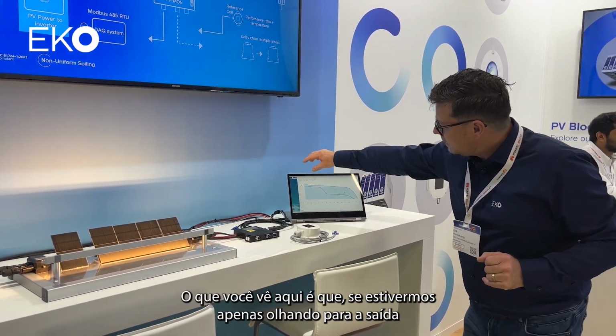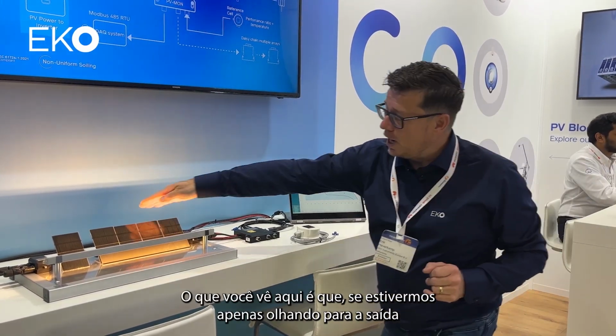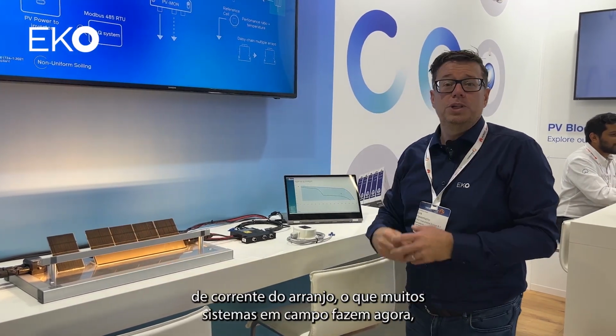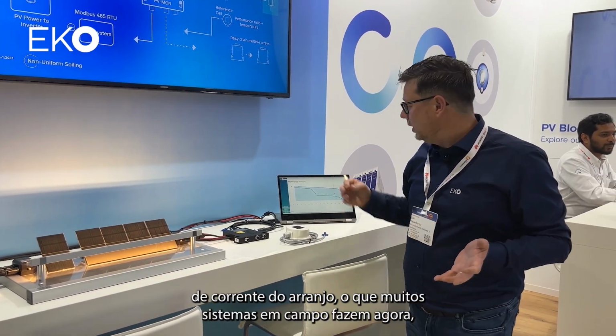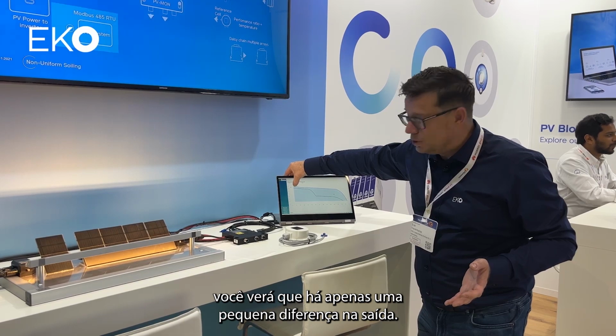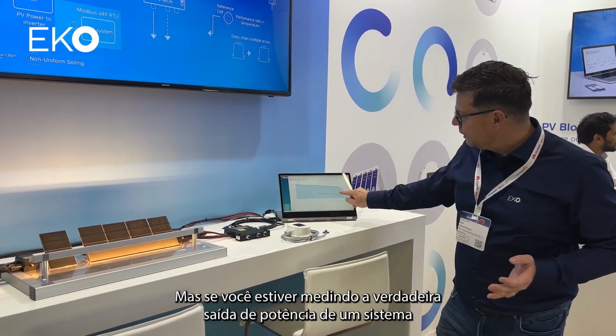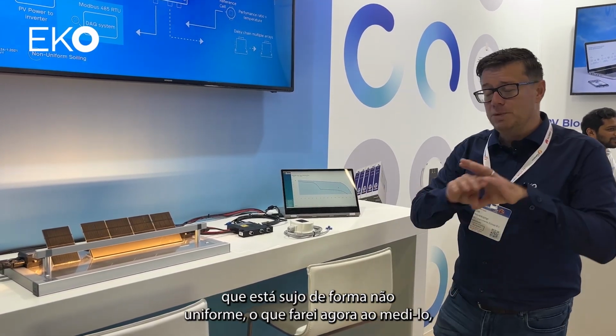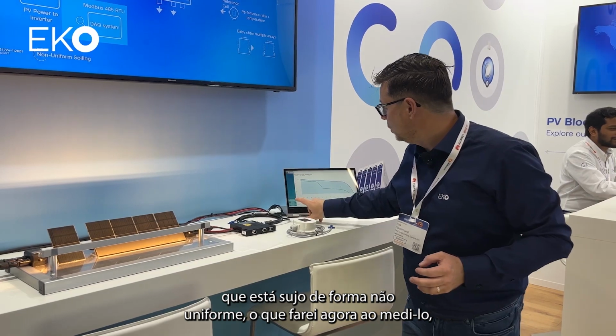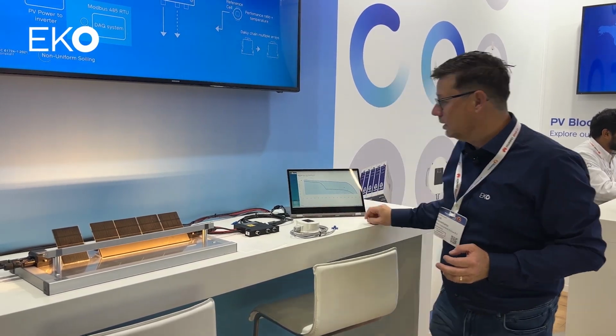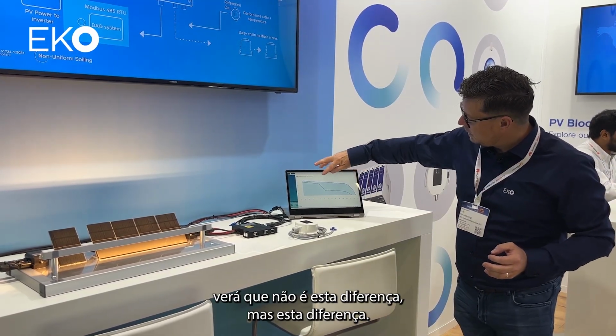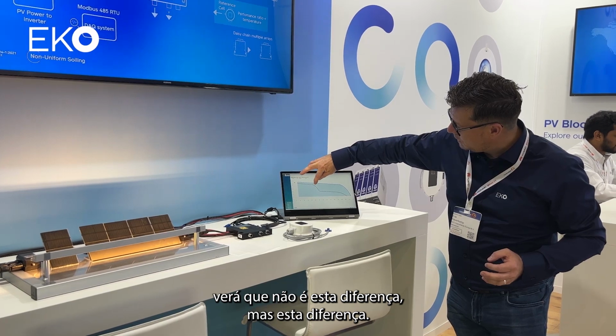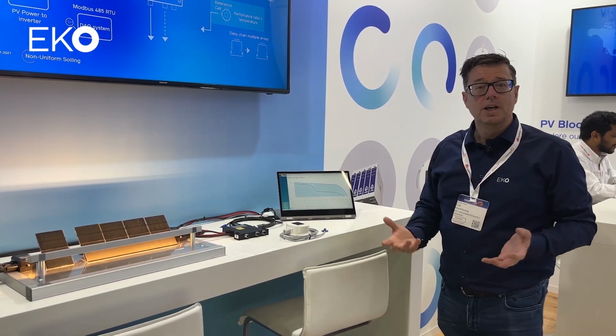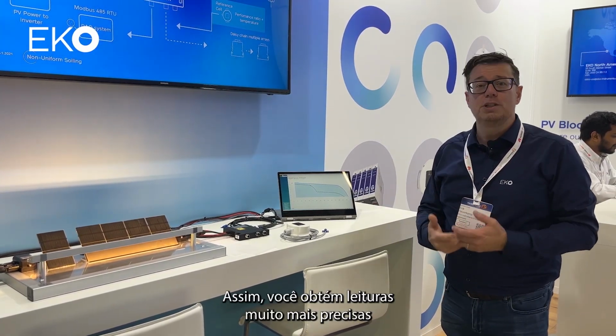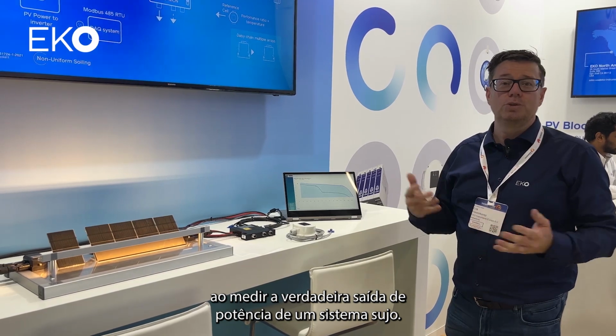What you see here is that if we are only looking at the current output of the array, which many systems in the field are now doing, then you will see that there's only a little difference in output. But if you're measuring the true power output of a system that is non-uniformly soiled, which I will do now, I will see that it's not this difference, but this difference. The difference is much higher. So you're getting much more accurate readings by measuring the true power output of a soiled system.